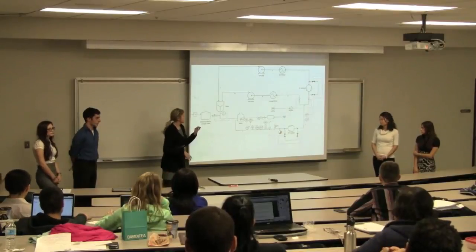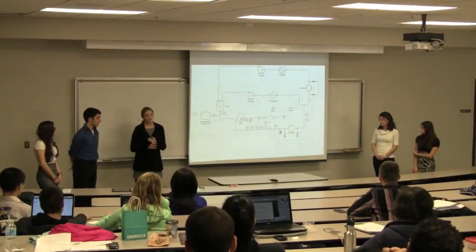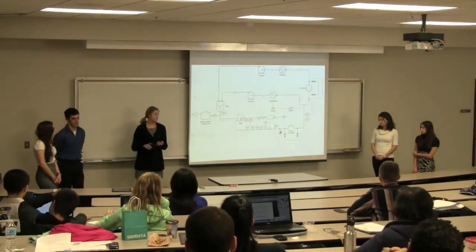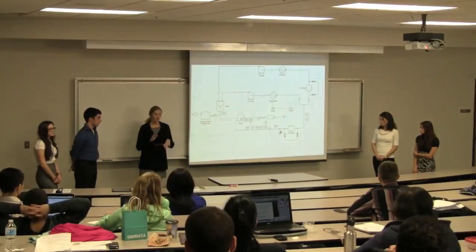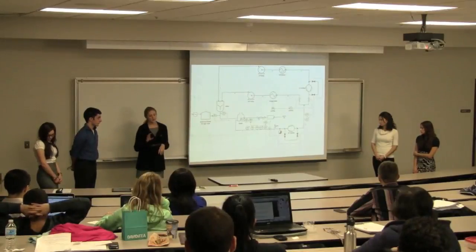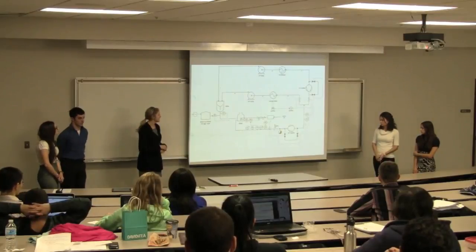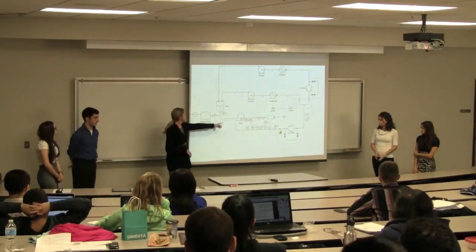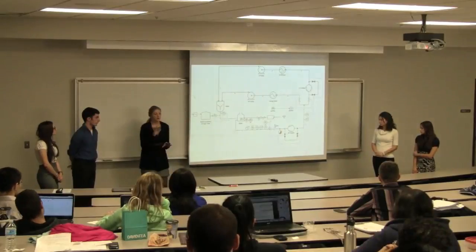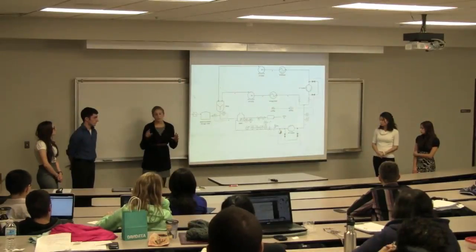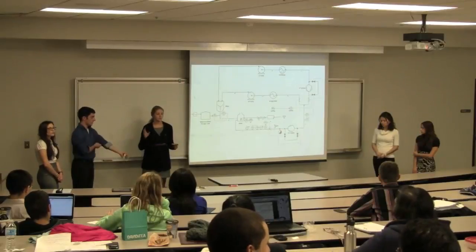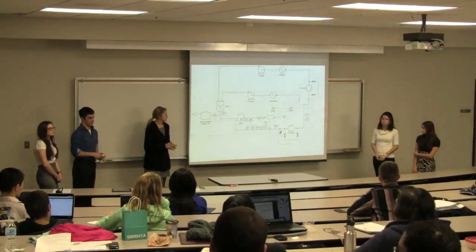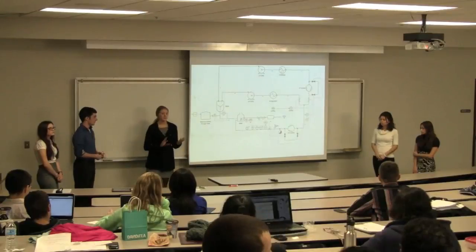For shutdown, it's a little bit different because we have to get that purge gas in there. We're going to use either nitrogen or dehumidified air. As you're starting to ramp down the boiler, you're going to have to replace that steam flow with the purge gas, and then run the system with the purge gas while everything else is at full capacity. You also have to make sure it's not connected back into the boiler. Once it's all purged, you can slowly ramp down your equipment, making sure all that moisture is removed, and you also prevent any damage from ramping it down too quickly.